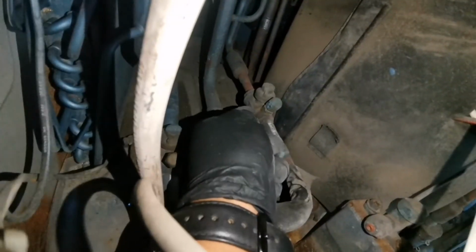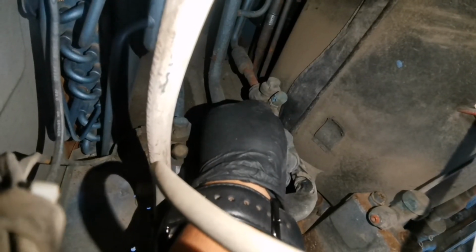Alright, so we'll put in a 1/2 inch. I think we'll just put a 1/2 inch flare on with a ball valve over here. That way, if the dryer gets clogged up, we can isolate by closing the ball valve on this side and closing the ball valve that's on the unit. And as you'll see, this port is in the front of the valve, which means it gives us access to this section here. So that way we can vacuum this little section here, isolating it from the entire system.